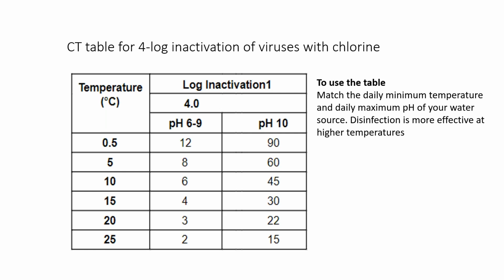So the pH and the temperature, and you notice that at lower temperatures, disinfection is less effective, so we need higher CT values, whereas at warmer temperatures we need lower CT values. Now we'll give an example here.